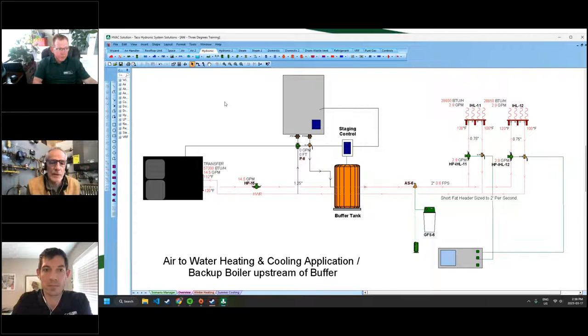Yeah, so then the buffer tank can serve the ModCon boiler there. And where I would like to see that is if you have micro loads, if you have loads that are smaller than what the turndown of the boiler is, then it's nice to have that, let's call it a battery, is really what that buffer tank is. It's just going to store that energy in there. So really what he's done on those two drawings is just move the boiler to the left side of the buffer tank instead of the right side.